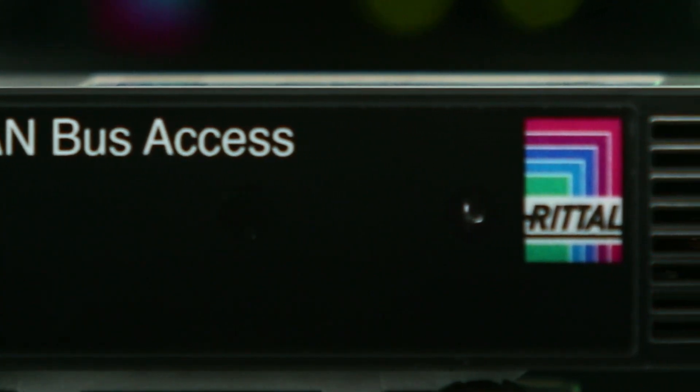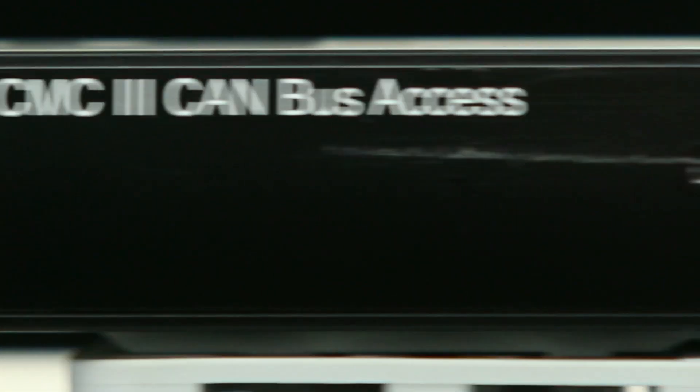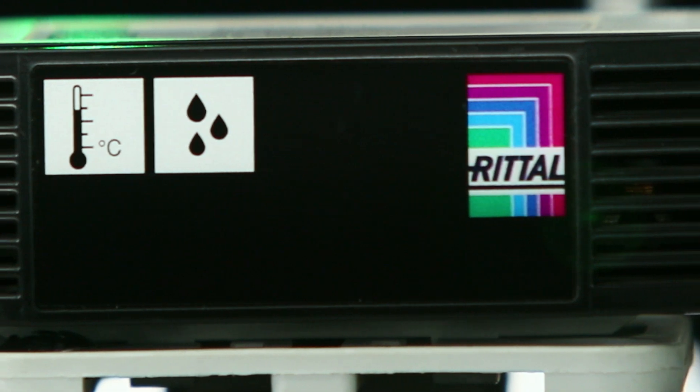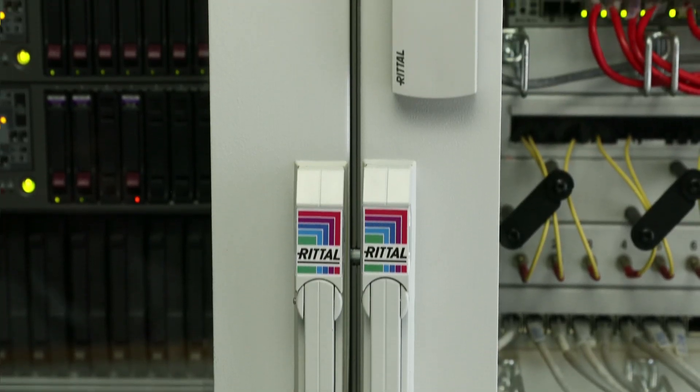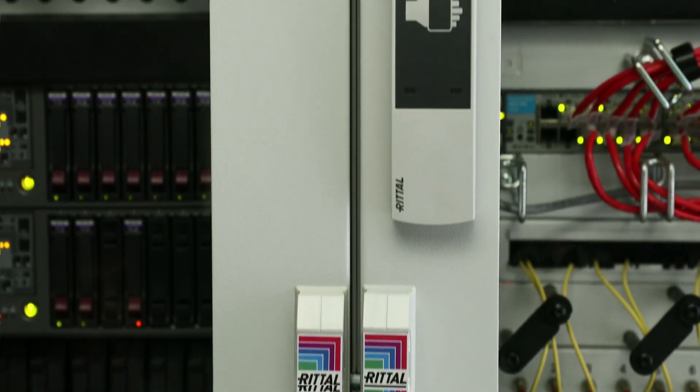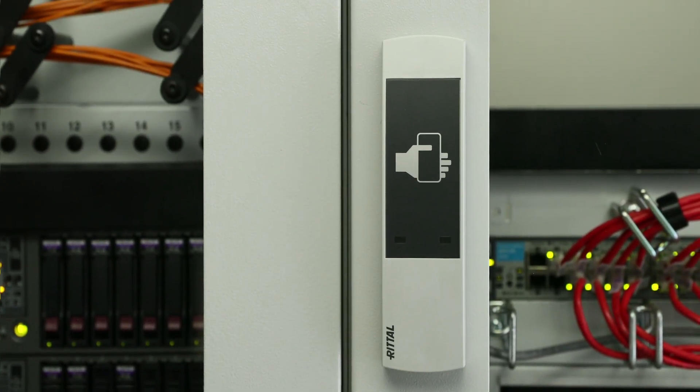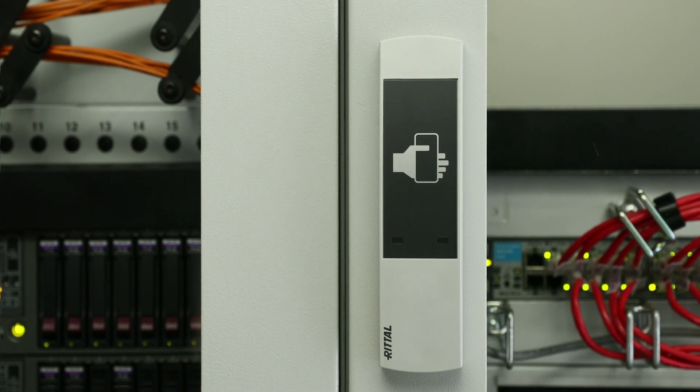It monitors and alerts the temperature, humidity, and water leakage. It alerts vandalism or unauthorized access through visual CCTV monitoring, email, and SMS media. The CMC3 inside the rack also monitors the access control with biometric or smart card or coded lock, and can automatically open the rear door when in need of emergency cooling.